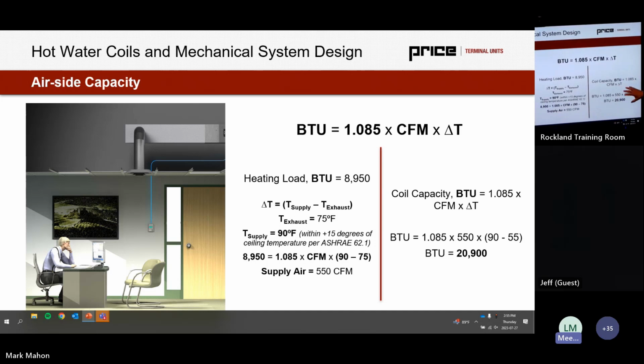I can then plug that into a coil capacity because I know I need to reheat my coil from 55 degrees up to 95 or up to 90 degrees in order to make this work. And that's 21 MBH that I'm going to need of coil capacity to achieve that load on design day.